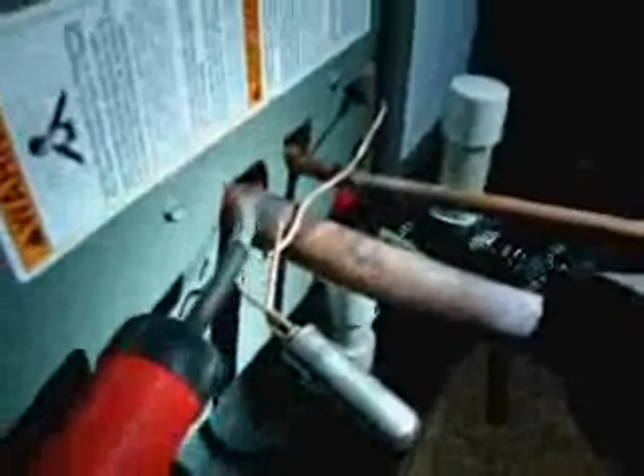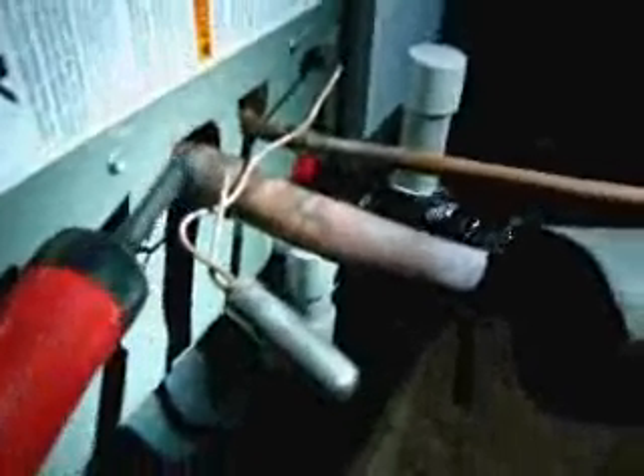This is the upstairs air handler. This is the negative side of it. So you can see the smoke is being drawn into the air handler cabinet while the fan is running at the line set connections, but also at the evaporator drain connections too. So it is drawing in the hot, humid, dusty attic air, getting the evaporator coil dirty from the outside dust and the attic dust. But more importantly, it's reducing the capacity and the efficiency of this air conditioning system, both in the heating and the cooling mode, because it's drawing in outside air.